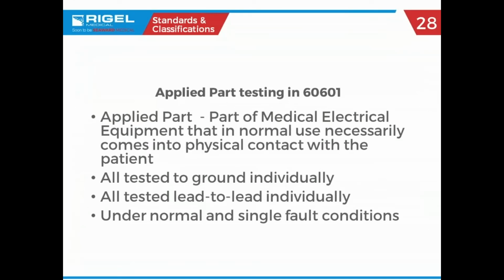So, applied part testing, 60601. I just kind of talked about this, I'm ahead of myself. You test each one to ground individually, and you test each one lead to lead individually. What I forgot to say a moment ago is you do that under normal operating conditions and under every single fault condition: open neutral, reverse polarity, open ground. So now you just multiplied all those tests by 3. It takes a long time to do electrical safety with this standard.